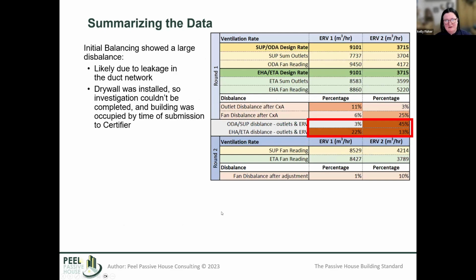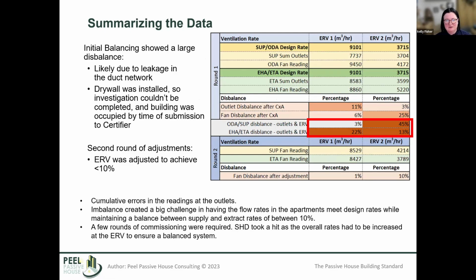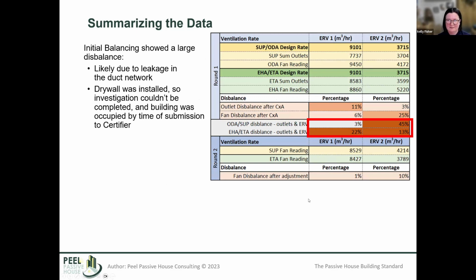So I have an example here of a project that had really terrible duct leakage with the initial run. I've got this table here where we're looking at the first round of commissioning. We received a really lengthy commissioning report for this particular project. When you sum up all of the airflow coming out of the outlets and then the airflow coming out of the fan itself at the ERV, there was a huge discrepancy. You can see in this little red box, this is over 2 ERVs, we had a highest imbalance at 45%. And this was likely due to excessive leakage through the duct network.